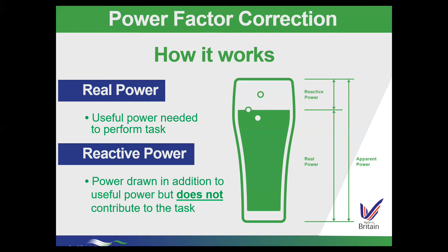So if you concentrate on the center numbers there where the example is, this is a typical industrial load. And this is something we get very, very often. If you think of power factor being a level of efficiency, it's operating at 0.8 power factor or 80% efficient. That would create what we call a KVA, which most supplies are rated on, of 1,250 and around about 1,700 amps. That exact same load, just by adding power factor correction and not changing anything else, as you can see, has reduced the KVA by about 240 and the current by 334 amps.